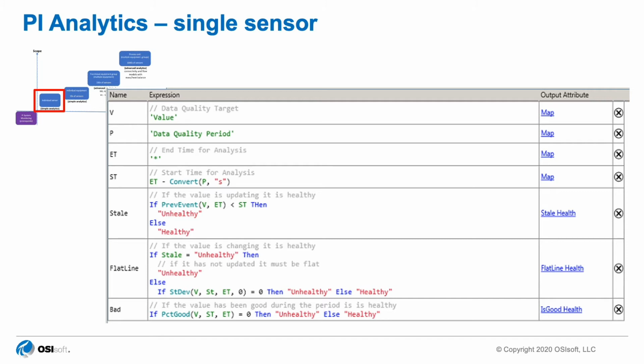Were you thinking of anything else? I was thinking of the ability to apply the same calculation if you need to check a large number of individual tags. I appreciate that if you take a sample of tags from a particular data source, that's a pretty good indication that the data source is functioning properly. But there are still some tags where you're going to want to check the individual tag to make sure that it's not stale or flatlining or having bad quality. And I'm just looking at this and I'm saying, if I've got to apply this to thousands of tags, that looks like a lot of work. Not at a template level, because these calculations are deployed using templates. So as long as you stick to a template-based deployment, it is not a tedious task. All right, that's what I was trying to get to.